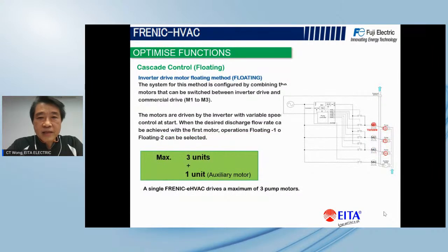Another method is the floating type. You can vary the M1. First, M1 will vary up to maximum speed. If the demand is more than that, then you need to call for M2 to start, right? From here, you can see that the inverter will release M1 and cut it in direct online, followed by M2: soft start M2 by the inverter and vary M2. Similarly, if the demand still cannot be fulfilled, you can go for M3. Similarly, M2 will be released direct online, followed by M3. So this is, as I say, the floating method on the cascade.